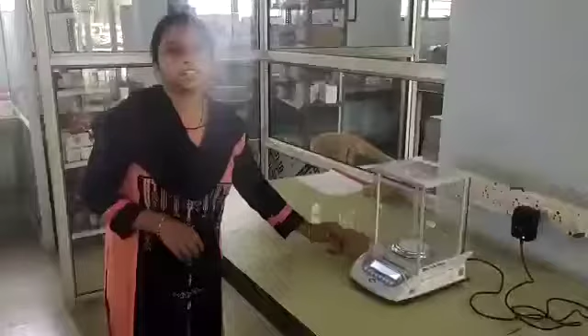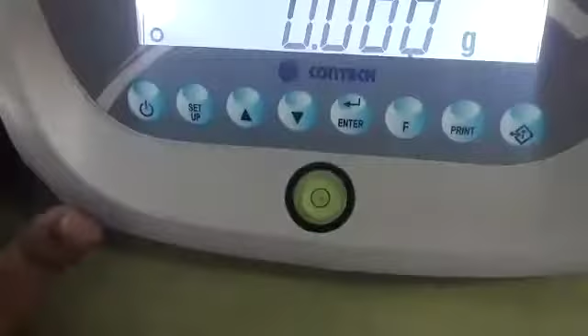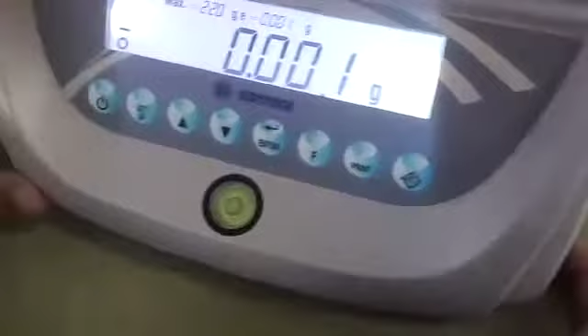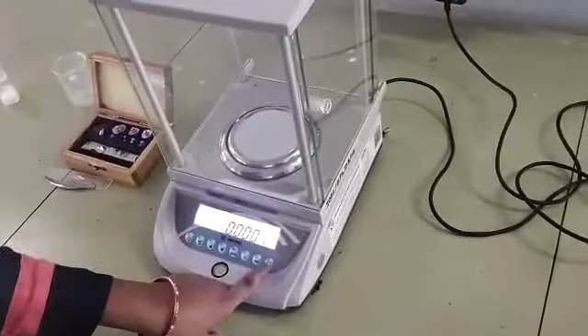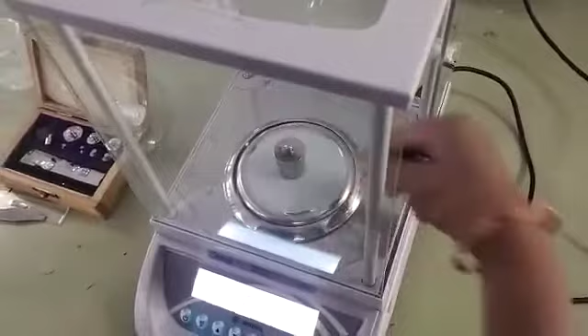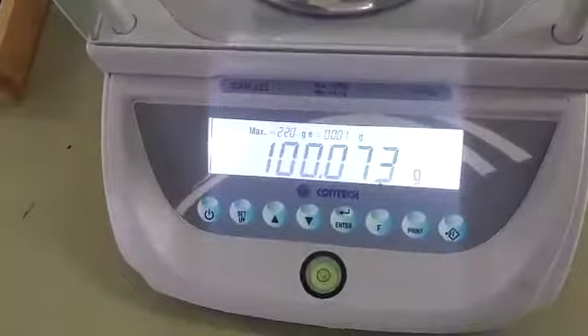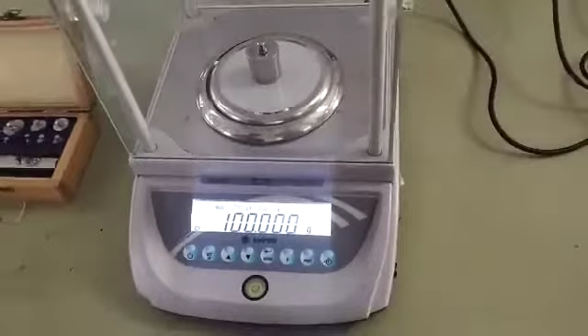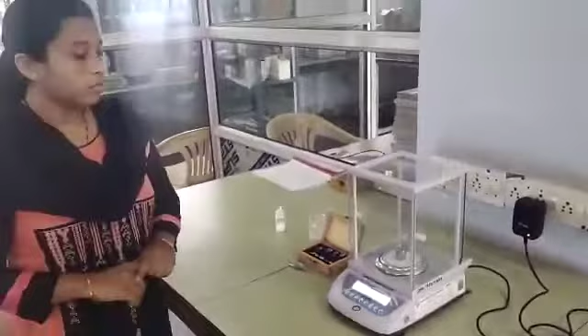Let's see about the calibration. For calibration, we ensure that this bubble is in the middle of this ring. If not, adjust it with the help of this screw. You see that the bubble is in the middle of this ring. Keeping the tare button, place the standard weight of 100 gram on the pan. Wait until it is stable. Press the F key. The display shows calibration done. This is all about calibration of the analytical balance.